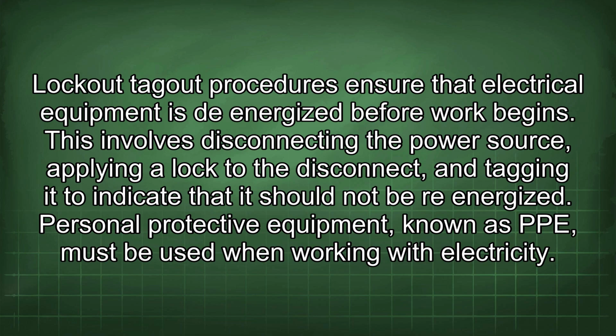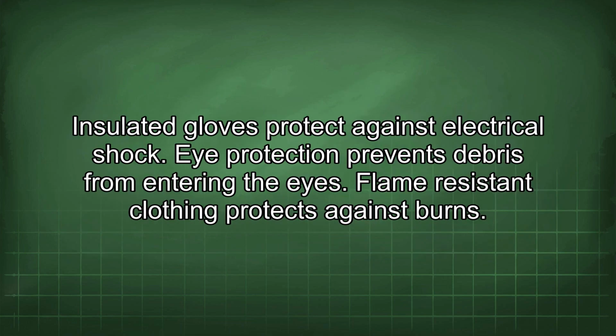This involves disconnecting the power source, applying a lock to the disconnect, and tagging it to indicate that it should not be re-energized. Personal protective equipment, known as PPE, must be used when working with electricity. Insulated gloves protect against electrical shock. Eye protection prevents debris from entering the eyes. Flame-resistant clothing protects against burns.